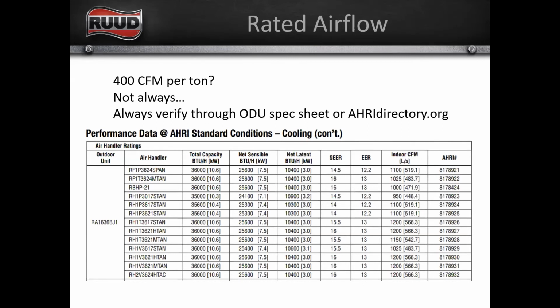So you can get this information from the outdoor unit spec sheet, and that's going to list the most popular matchups, or every matchup will tell you rated airflow at ahridirectory.org. So if you don't know what that matchup is, you don't know what that rated airflow is, look in the spec sheet. If you don't see that matchup in the spec sheet and you know it's a valid match, you're going to have to go to the AHRI directory to look it up. But here's an example, right?